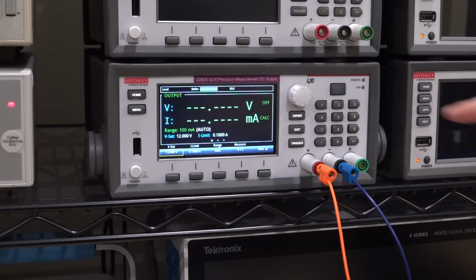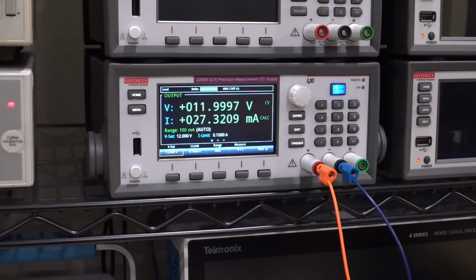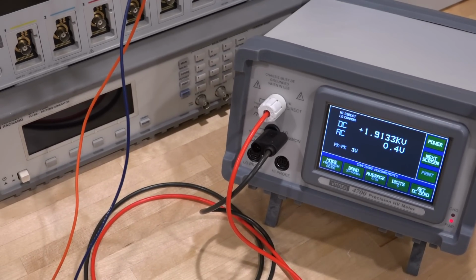Okay, let's give it a try one more time. And what do we have? Look at that, it started up, and now it's burning 24 milliamp. So it's significantly more, about 10 times more. And it is connected up exactly like before, and check it out, 1.9 kilovolt. That's what we're getting at the output, which is what we were expecting to see.